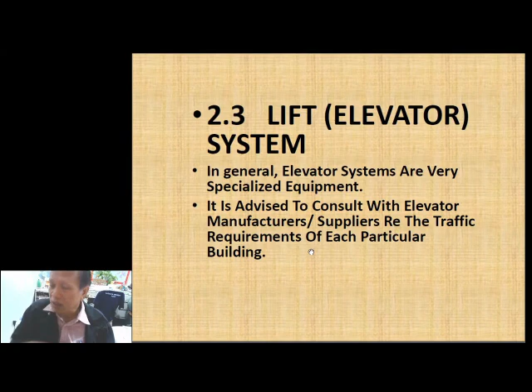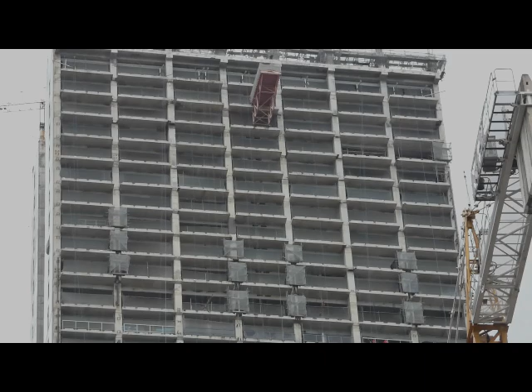Okay, so I'm going to give you 3 samples. Again, a 37-story mixed use building has 4 units of 1,200 kilogram elevators, each with 15 kilowatt or 20 horsepower drives. Now this 22-story building is the same, but it only has 2 elevators. Here in the 37-story, there are 4; this 22-floor building only has 2.